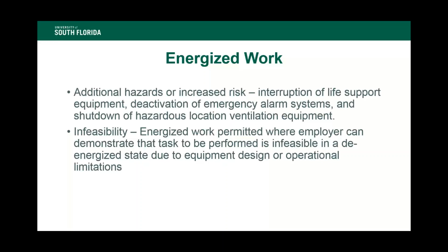Like I said earlier, sometimes there are situations where we're not able to work strictly in a de-energized situation or an electrically safe working condition. There are times which we might find that if we kill the power, we might be interrupting life support equipment, or we might be deactivating emergency alarm systems, or possibly even shutting down vital ventilation equipment servicing a hazardous location where they rely on that ventilation to prevent a greater catastrophe from occurring, such as an explosion.